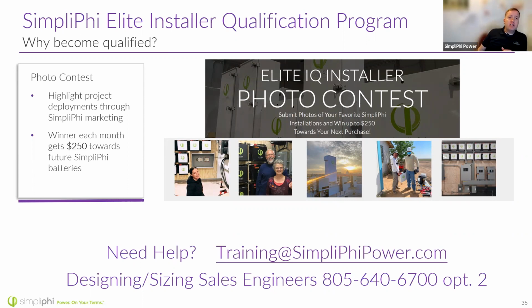What can happen is we can use those UL 9540A certificates to supersede the NFPA requirements, because the language says if you don't have a 9540A, you have to adhere to the NFPA 855 requirements. But if I can prove with this UL certification that I'm safe to do this, you can get an AHJ that properly understands it and prove to them they don't have to adhere to that, since I do have a 9540A cert. But even so, like Chuck mentioned earlier, you always have to defer to the AHJs—they all interpret it differently. I do see that driving things outside as well.